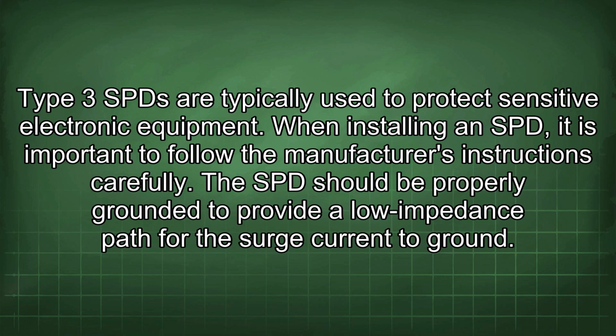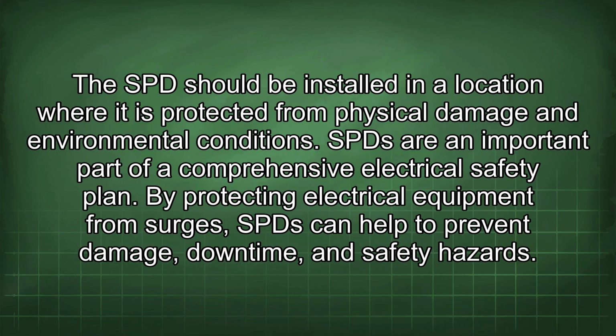When installing an SPD, it is important to follow the manufacturer's instructions carefully. The SPD should be properly grounded to provide a low impedance path for the surge current to ground. The SPD should be installed in a location where it is protected from physical damage and environmental conditions.